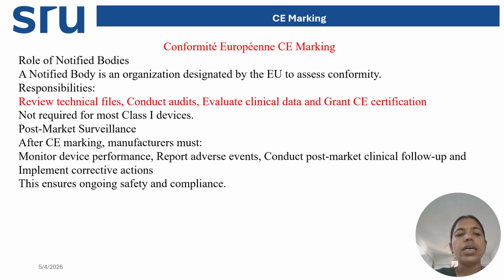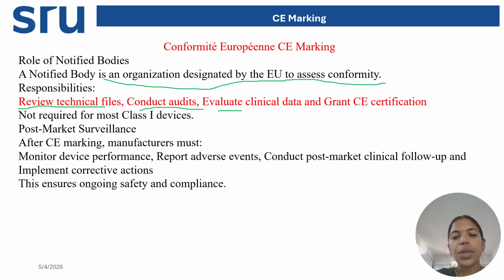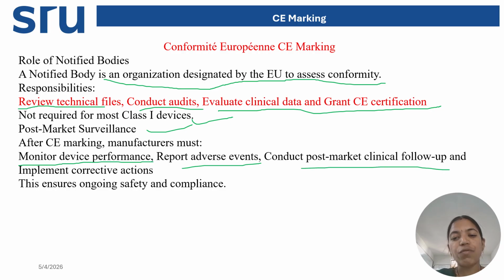So what are the notified bodies? What is the role of the notified bodies? A notified body is nothing but an organization designated by the EU to assess conformity. Its responsibilities are to review the technical files, conduct audits, evaluate clinical data, and grant CE certification. It is not required for class 1 devices. Post-market surveillance: after CE marking, the manufacturers must monitor the device performance, report adverse effects if it is not working properly, and conduct post-market follow-up. And if there is any problem, they have to implement corrective actions. This ensures safety and compliance for the improvement of risk to the life of the patient.